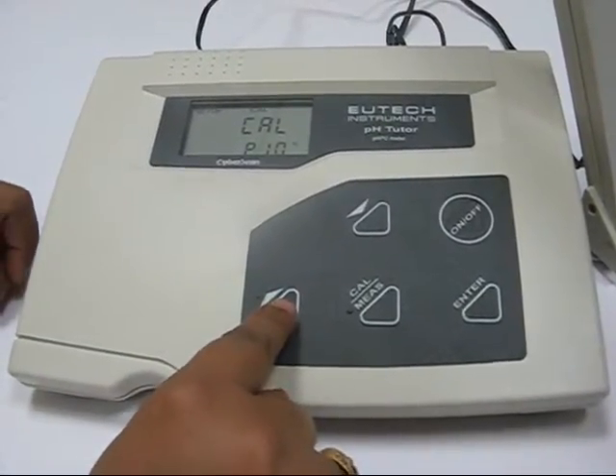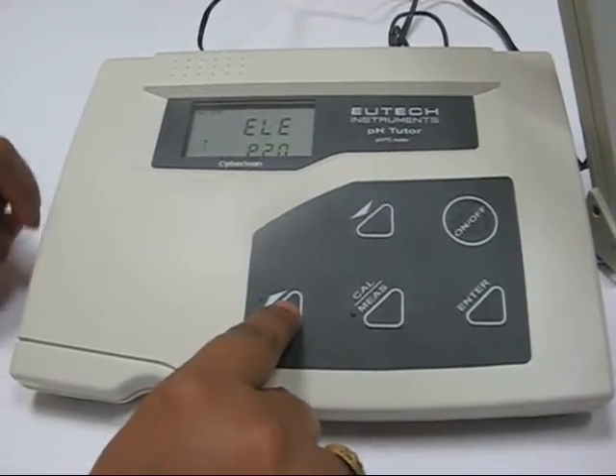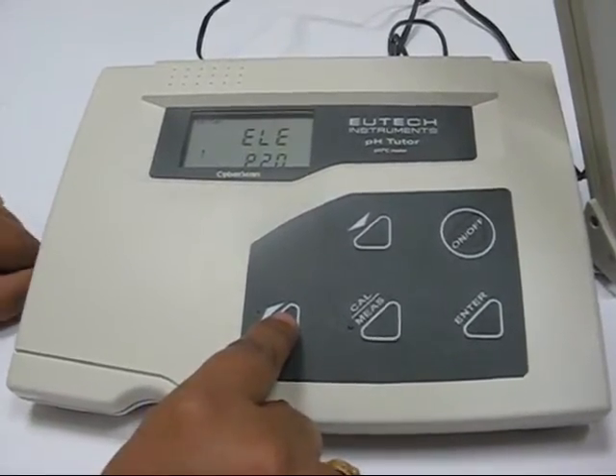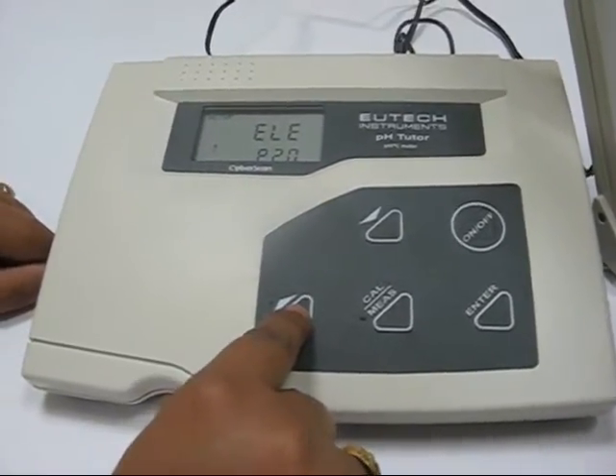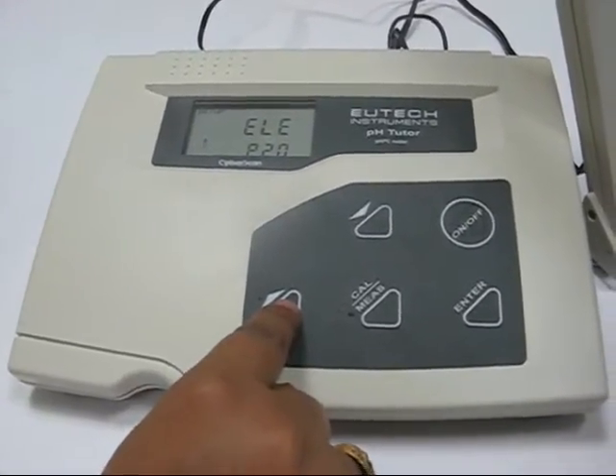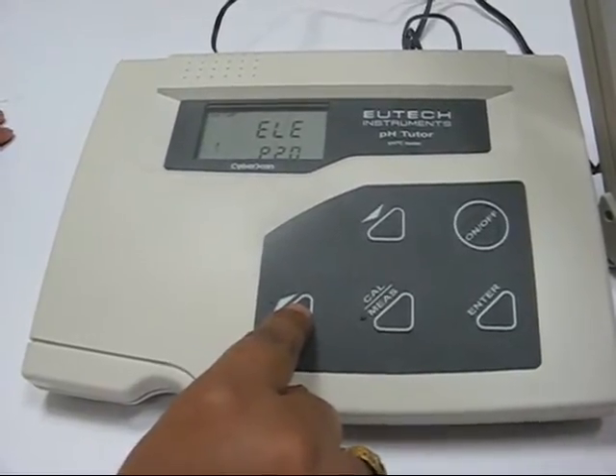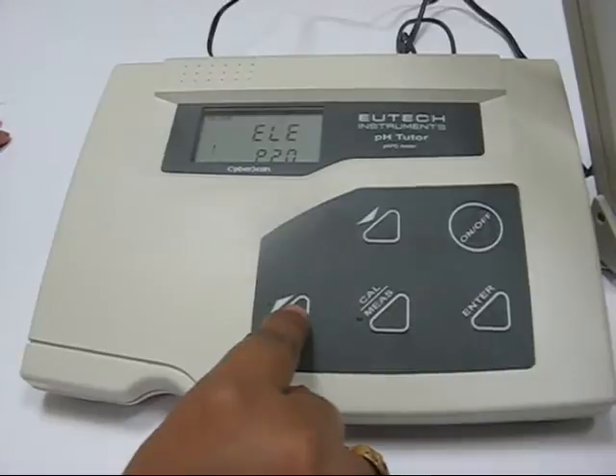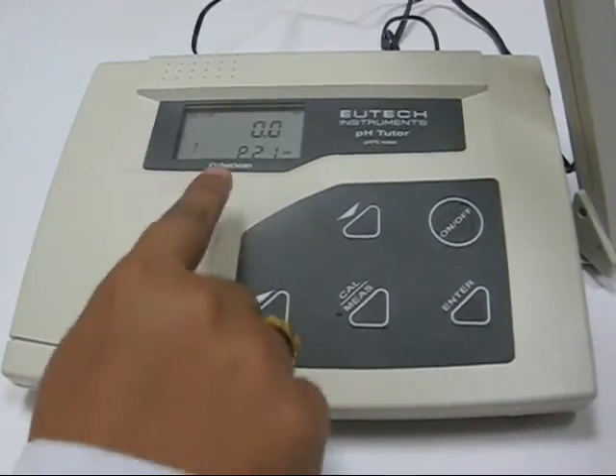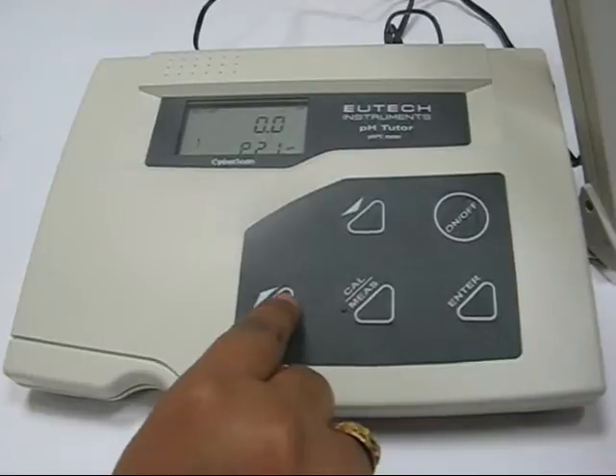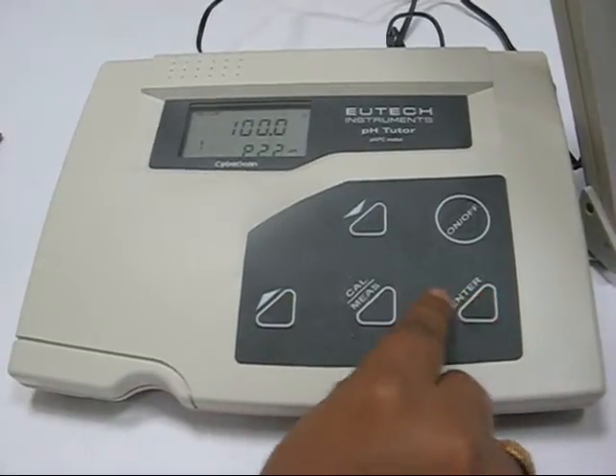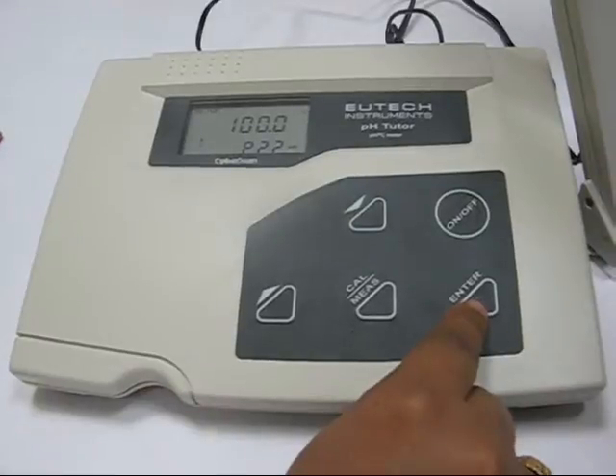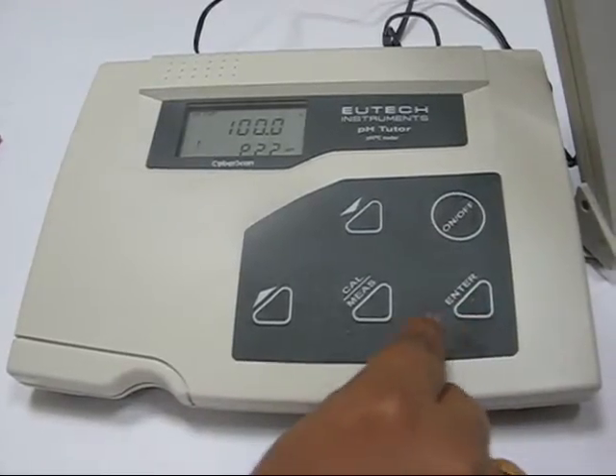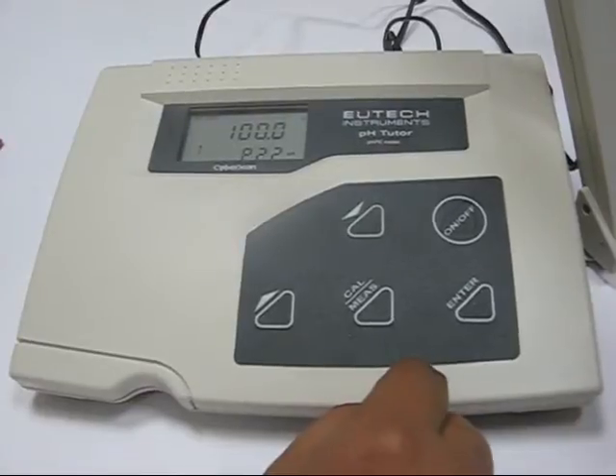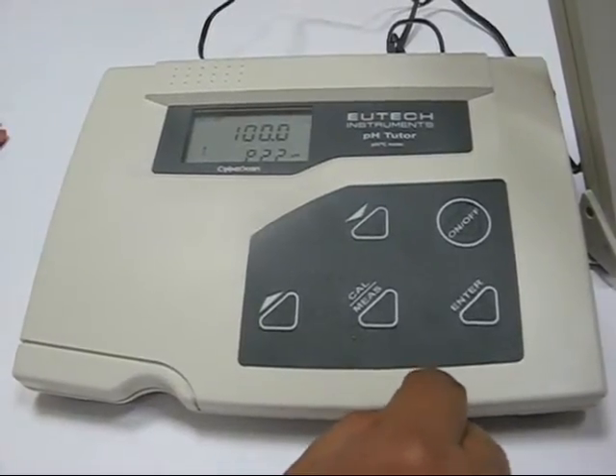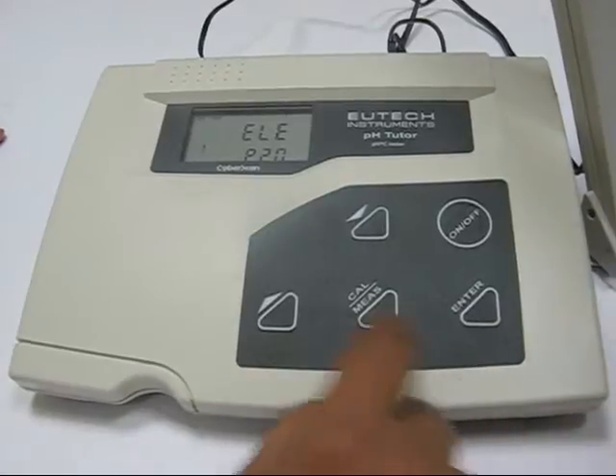Let's go to the program 2.0. This menu is actually where you have to get in to check the condition of your electrode after completing a calibration. In this particular case, since the instrument is just out of the box, it will show you the theoretical values, which are, press the enter key, 0 millivolts, which is the offset theoretical value, and 100%, which is the theoretical slope of the electrode. Now you will see these values changing after you have completed a calibration. We will come back to it a little later.